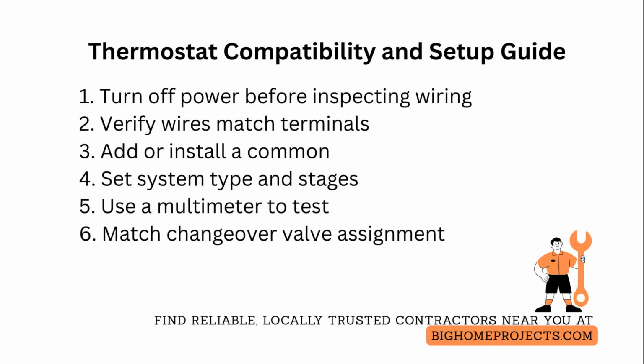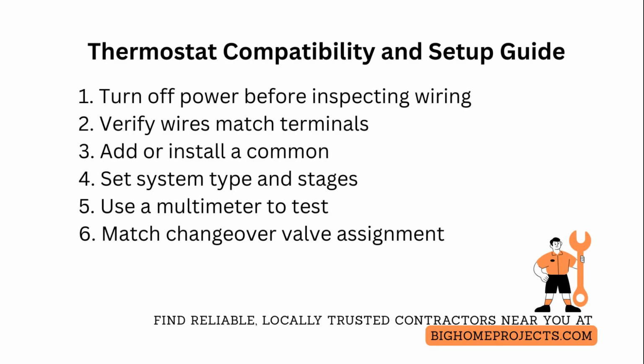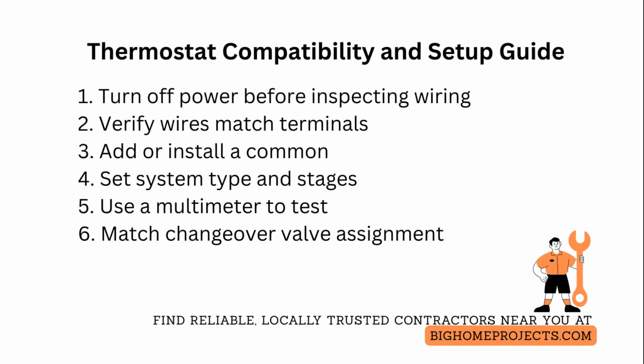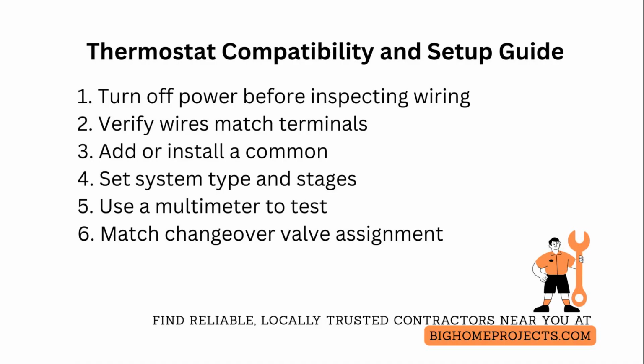Match wire colors to terminal labels and trace the common wire back to the air handler to confirm its presence. If you lack a common, add a common using a power extender kit or install a separate 24-volt transformer per manufacturer guidance. Next, check and set dip switches or on-unit configuration menus to the correct system type.